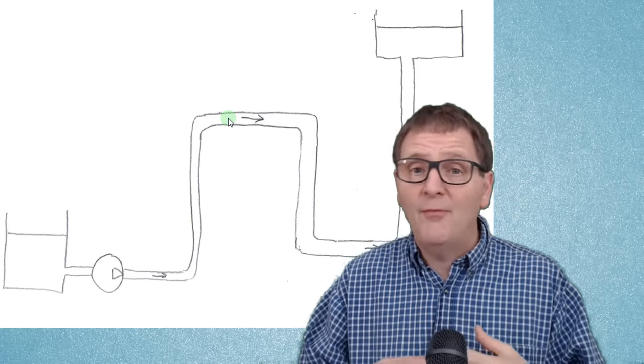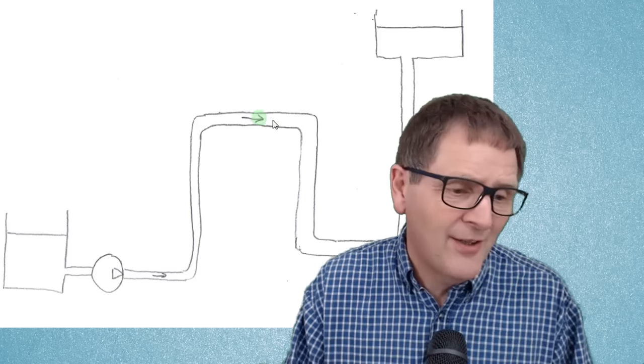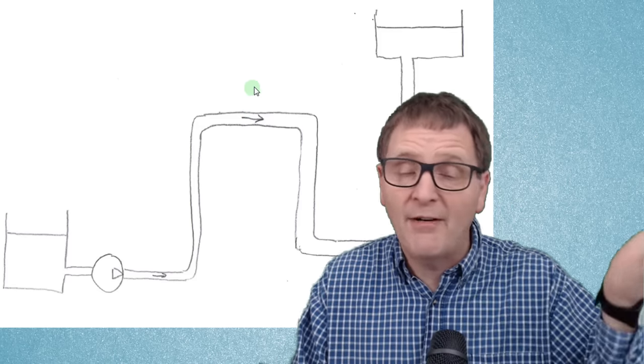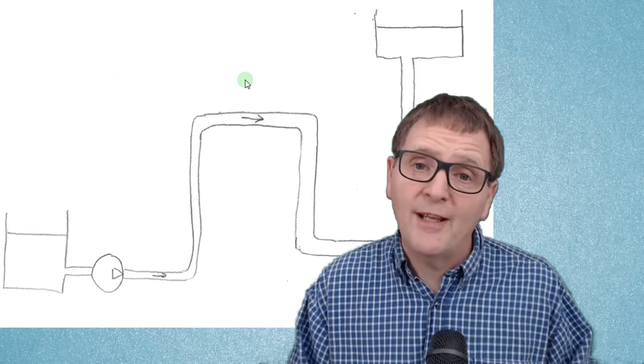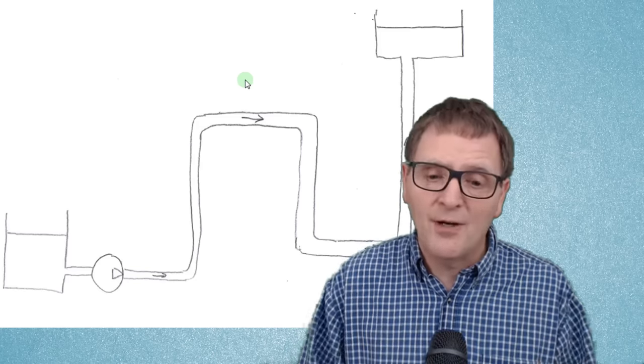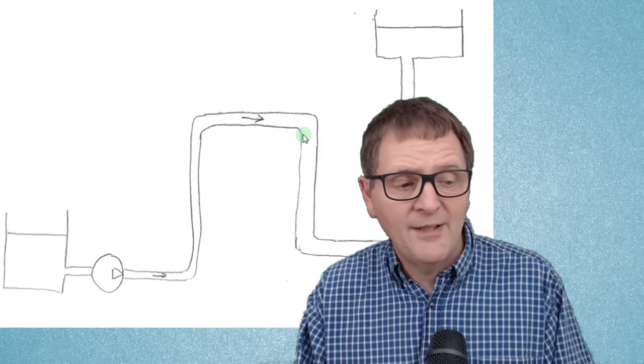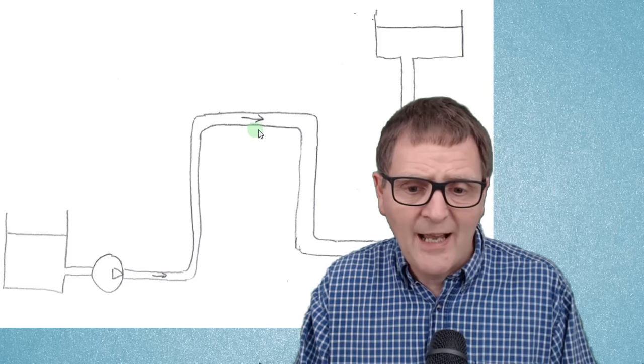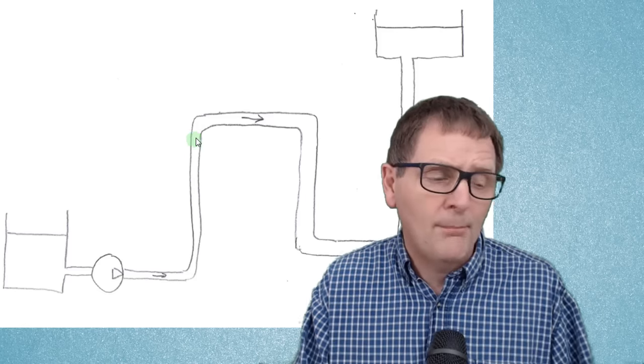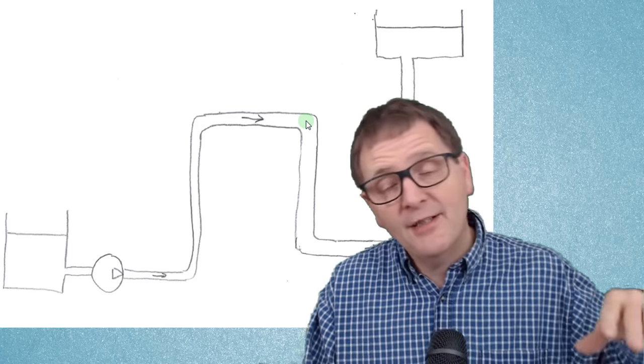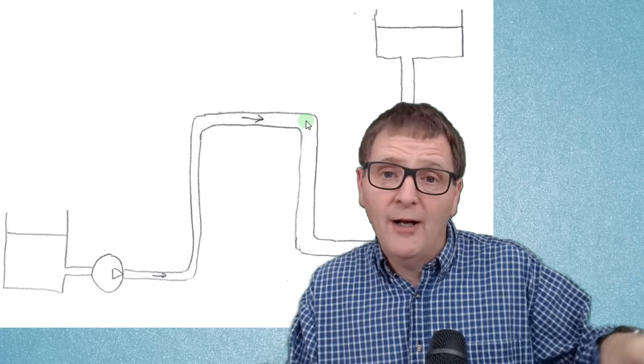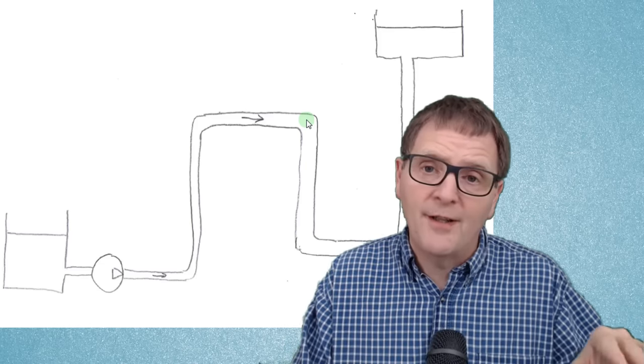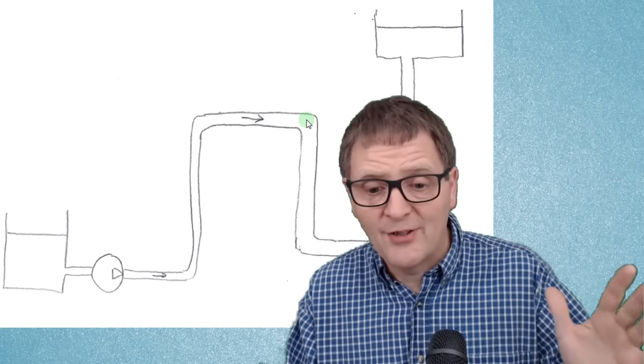If you've got high temperatures, water could actually vaporize — that's another type of gas bubble that could form. Or if the pipe is very high, the pressure drops and gas can come out of solution. There are lots of reasons why gas could come out of solution, and you'll find there is potential for the gas to get trapped at these high points. Even if the pipes are at a very shallow angle, there is still a high point, still a negative flow gradient, and still potential for gas to get trapped.